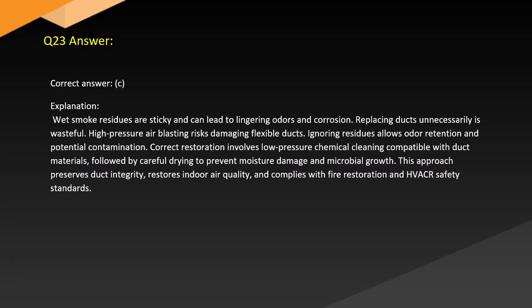Answer. Correct answer: C. Explanation: Wet smoke residues are sticky and can lead to lingering odors and corrosion. Replacing ducts unnecessarily is wasteful. High-pressure air blasting risks damaging flexible ducts. Ignoring residues allows odor retention and potential contamination. Correct restoration involves low-pressure chemical cleaning compatible with duct materials, followed by careful drying to prevent moisture damage and microbial growth. This preserves duct integrity, restores indoor air quality, and complies with fire restoration and HVACR safety standards.